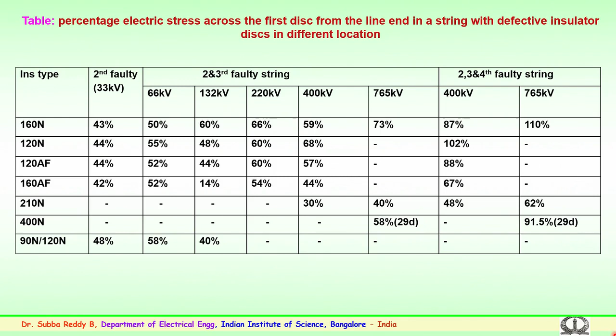This gives very important information. In case the insulator units are faulted after the middle of the insulator string, not much of a worry, whereas if the discs are faulted near the line end, after the first insulator, the second, third, fourth, it is very serious, and the utilities have to immediately take necessary action in changing the insulator and bringing down the stress level across the first disc insulators.